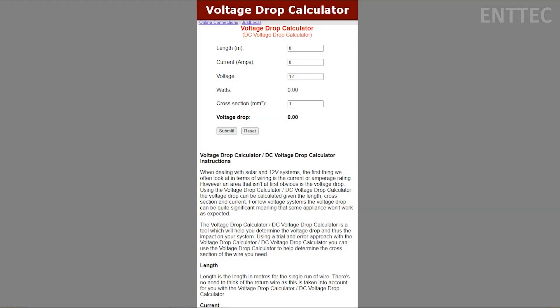Length. This one's easy enough. We're checking for the voltage drop in the cable so we need to enter the length of the cable from the power supply to the back of the tape where the connection is made. It's generally best to be a bit conservative here, so instead of five meters we'll put six meters, as a six meter length of cable will have a higher voltage drop than a five meter length of cable.